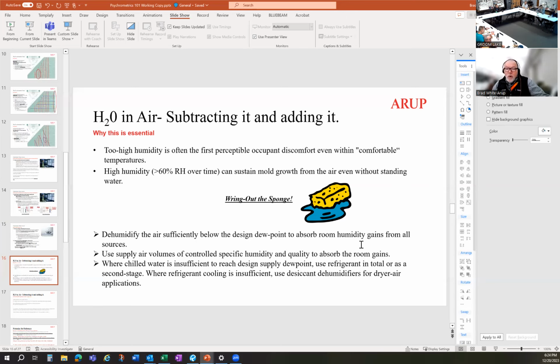So the air will come back to the unit at, let's say, 78 degrees, go through the fan, it might come off at 80 degrees, and they'll cool that down to 56, 57, 58, whatever's needed to cool the room. But it's not going to remove humidity, because there's no real need to, and there's no humidity to be removed to begin with. So they don't have a need to subcool it.